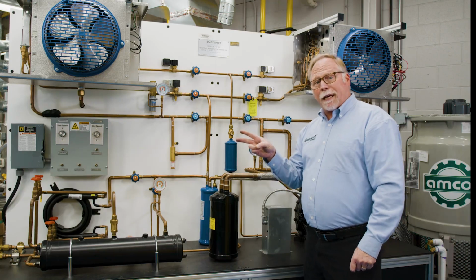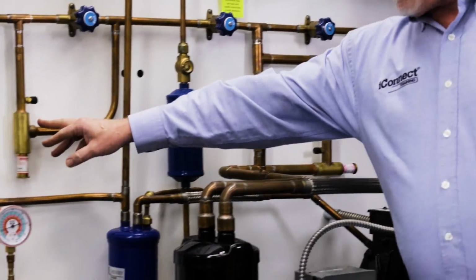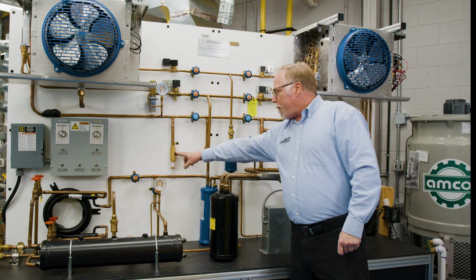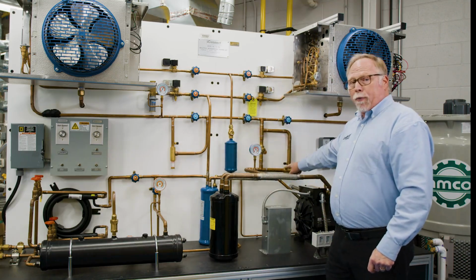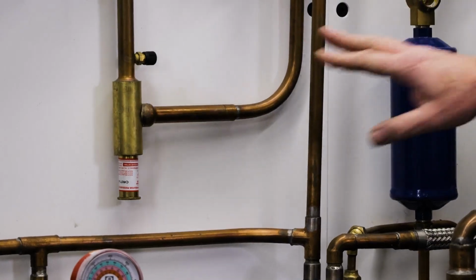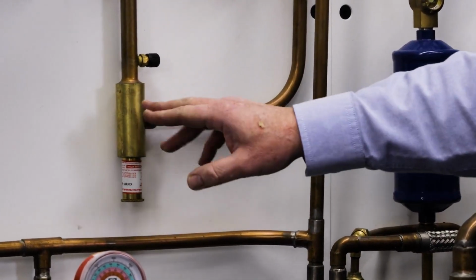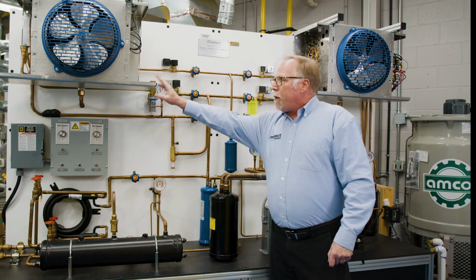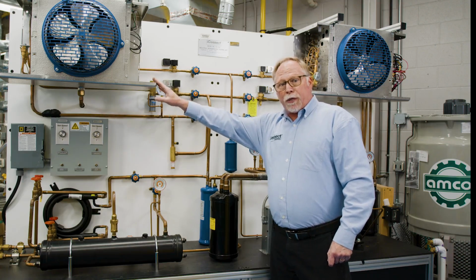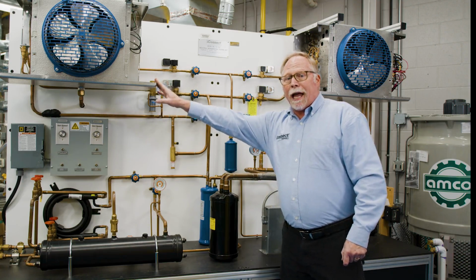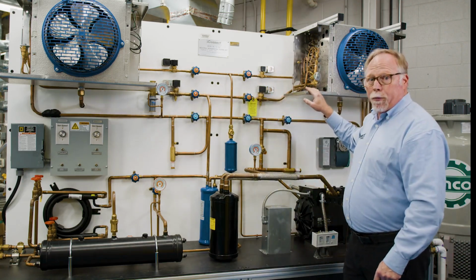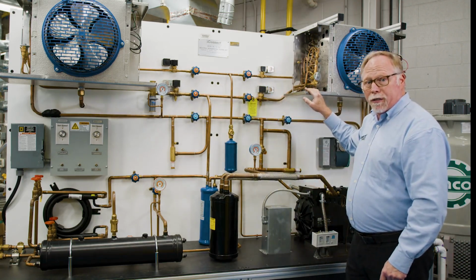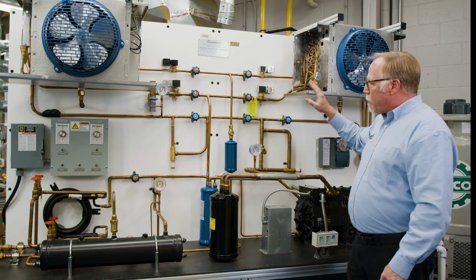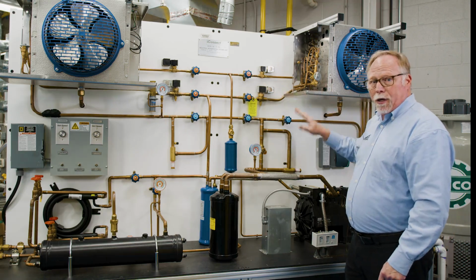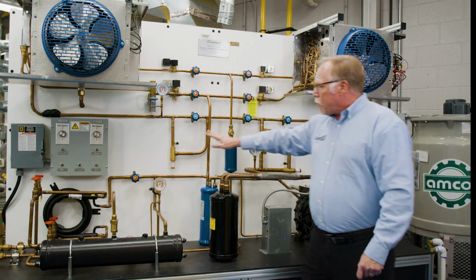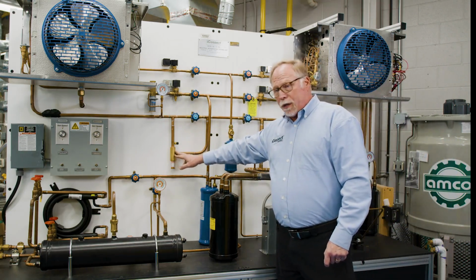The second lesson I'd like to teach about is the EPR valve. Now we've got one EPR valve per evaporator coil. But an EPR valve, remember, comes into play whenever it is used to keep up the pressure in the refrigerator coil, and it allows the freezer coil to get pulled all the way down to a lower saturation temperature. And that way we can control 2 different temperature evaporators with one compressor system. So we can teach about the EPR valve and its function.